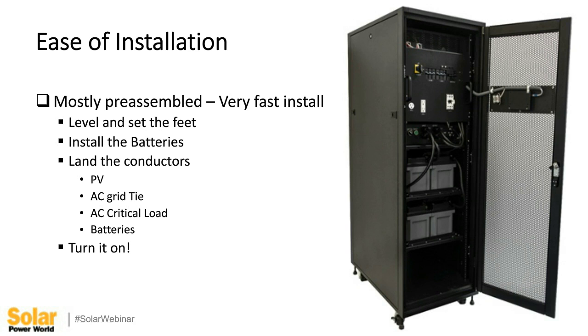Most of these will not be shipped with batteries installed. Lead acid is way too heavy to ship that way, and lithium-ion or lithium iron phosphate don't let you ship them installed under normal conditions—you've got to have a very controlled state of charge or depth of discharge, packaged separately and uniquely, so that if shipped in a container, it can only carry batteries similar to it. So be prepared to have multiple packages.